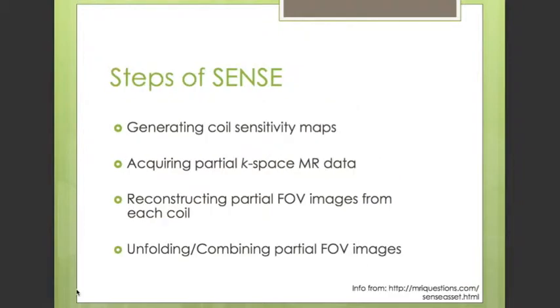The SENSE method consists of several steps. The initial step consists of acquiring the sensitivity maps of the coils. In order to map the sensitivity, a low-resolution full field-of-view image is acquired from each coil. These images are then normalized using the body coil image. After filtering, thresholding, and point estimation, the maps are generated. The maps represent the weighting of each signal acquired from various points, which later helps in removing the superposition of pixels from the original pixel.